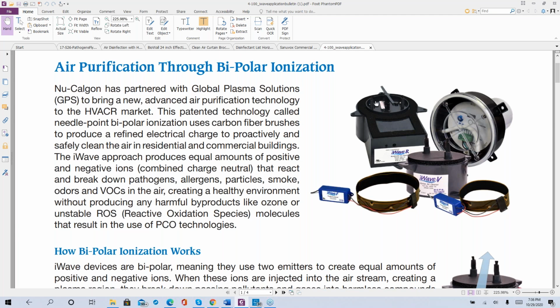carbon fiber brushes. You also want to make sure that these brushes are more than 2 inches away from any conductive material, because I'm not quite certain whether they will arc out, but they will disrupt the free flow of the ions. So it's not a good thing. So you want to make sure that these are mounted nowhere near anything that is conductive material. Typically, they want you to put them between the filter rack and the coil.